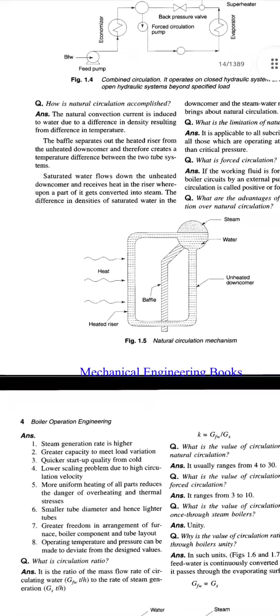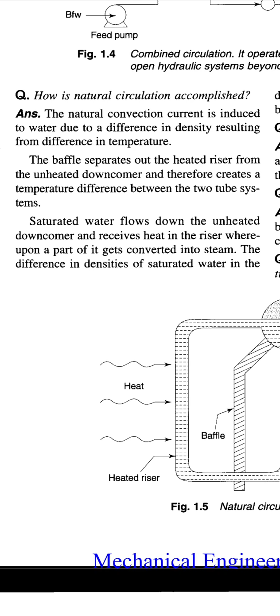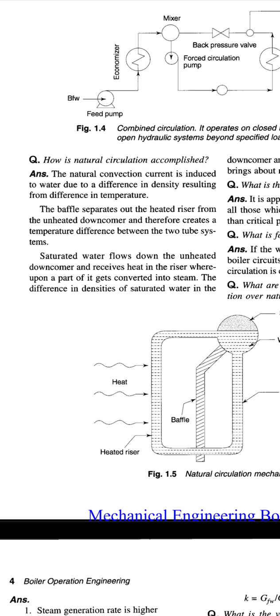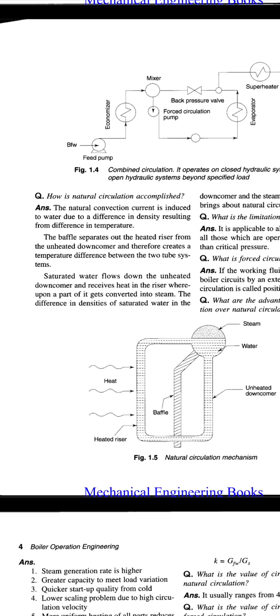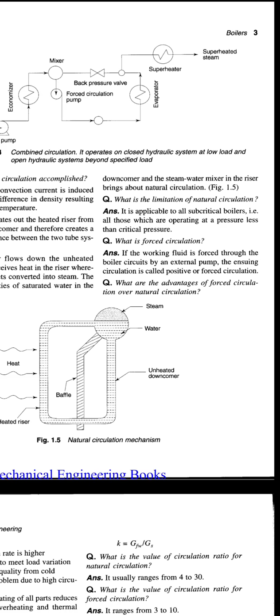So next question is, how is natural circulation accomplished? The natural convection current is induced in the water due to difference in density resulting from difference in temperature. The baffle separates out the heated riser from the unheated downcomer and therefore creates a temperature difference between two tube systems. Saturated water flows down the unheated downcomer and receives heat in the riser, whereupon a part of it gets converted into steam. The difference in densities of saturated water in the downcomer and steam water mixture in the riser brings about the natural circulation.